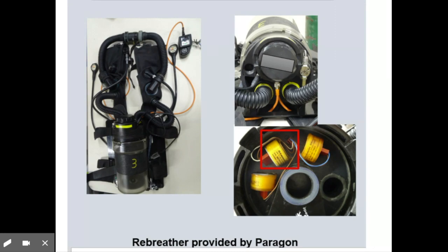And lastly, the O2 sensors pictured here are special sensors made by the consultant. This O2 sensor is slightly big and needs to be fully immersed in the flow of air. These O2 sensors could not be controlled by the team since the current control system could not be accessed.